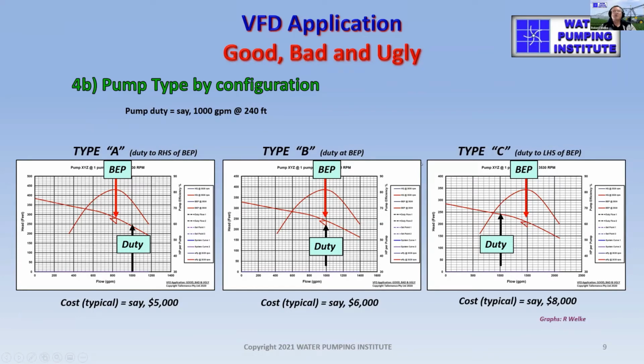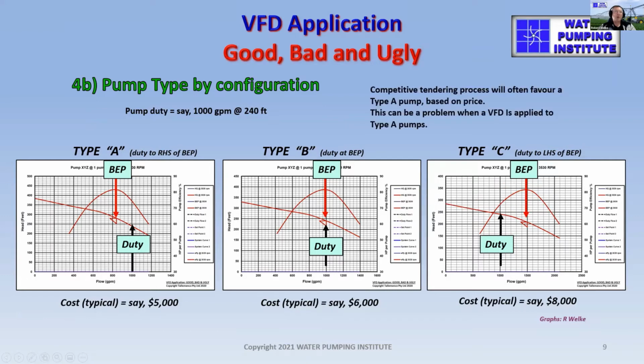Now, the most common pump you'll see out there is a type A pump. Why? Because if you call for a pump of a specific duty, you'll find that this configuration here will be the cheapest pump to sell that will give you the duty that's required. And so that pump tends to be a smaller size, whereas if you go to a type C pump, that pump will generally be much larger and therefore more costly. So on a competitive tendering basis, you will find that the type A pump will be the most common pump in the irrigation industry, where the duty is sitting to the right-hand side of best efficiency. There you go.